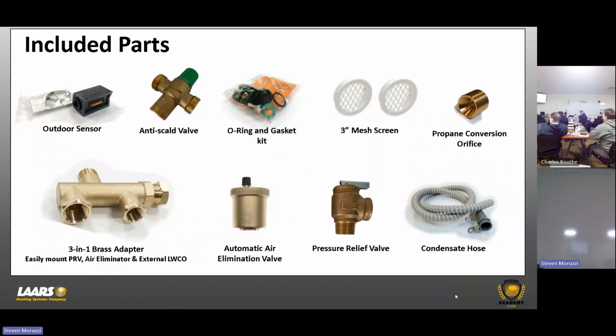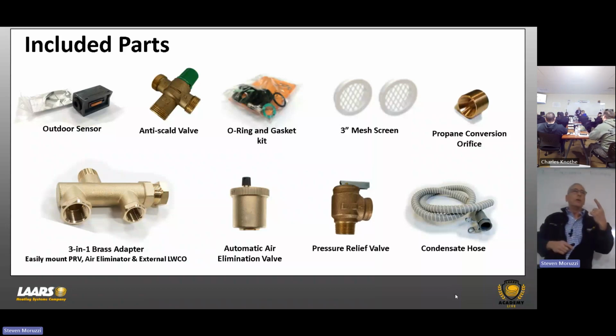We give you the 3-in-1 brass adapter, automatic vent, pressure relief, and the condensate hose. Okay. And that condensate hose, you don't have one handy. That condensate hose, you know what? When I get to the error codes, I'll show it then. Condensate hose has an orientation because we have a vacuum breaker right on it. Okay. So that wants to be in the up position. Keep in mind, the heat exchanger and down below, that condensate, if that vacuum breaker was facing down, I'm now going to dump condensate on the floor. All right. So we'll show you one of those as well.